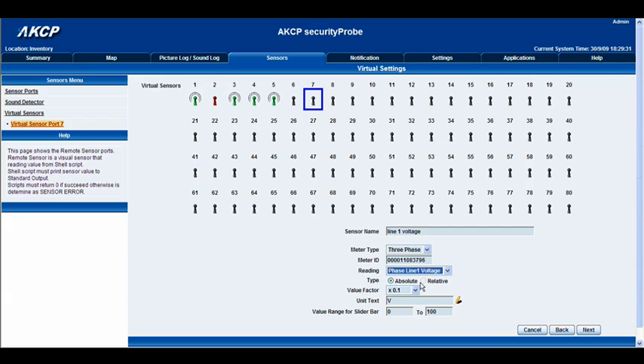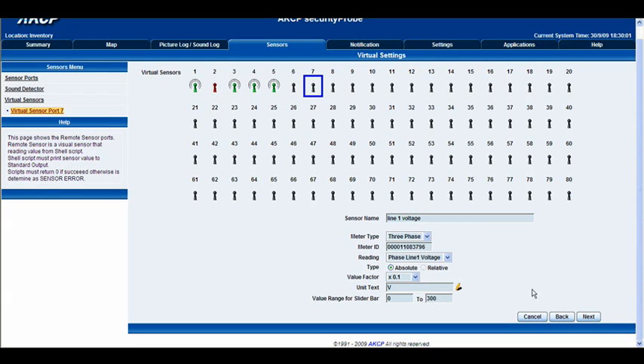Below that we have our reading, and again we've got a lot of options here. Since we're measuring the voltage on line one, we're going to select phase line one voltage. Then we have the type, where you can choose relative or absolute — we're going to leave that as absolute. We have our value factor, currently set at times 0.1, and we'll leave it like that to get a reading of voltage. The unit text we've entered as 'V' for voltage, and then we have our value range for the slider bar, which we're going to change from 0–100 to 0–300. Then we'll click next.